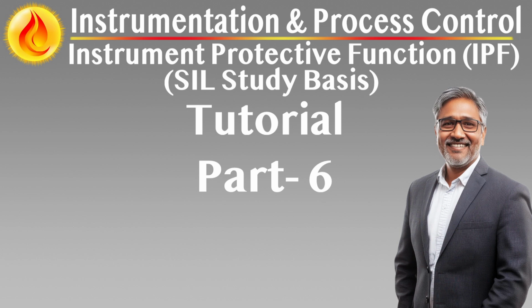Maintenance overrides in IPF implementation. Balancing maintenance flexibility with safety assurance. Maintenance overrides, also referred to as bypasses, inhibit commands, or force signals, are temporary measures used to disable or suspend an instrument protective function, IPF, or one of its components during testing, calibration, or corrective maintenance.